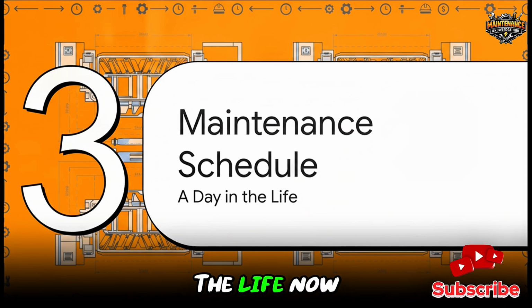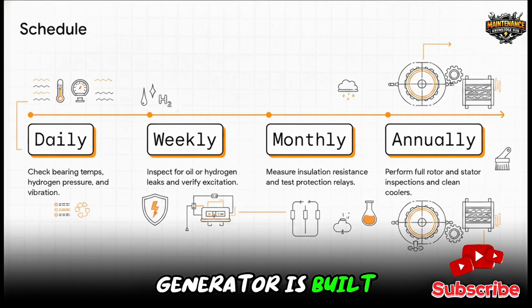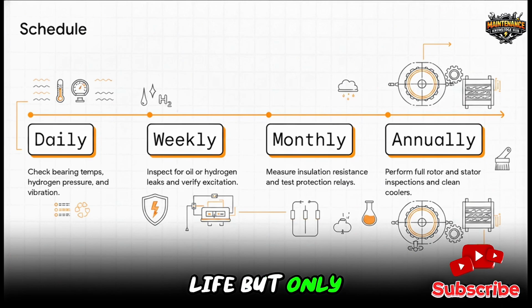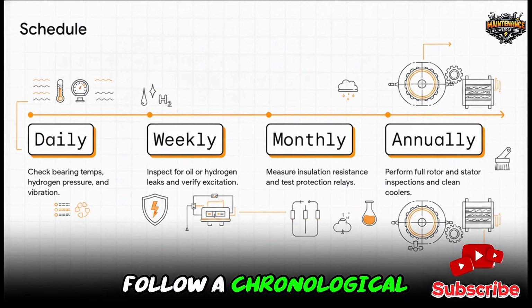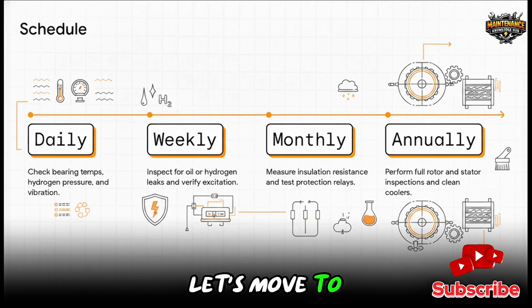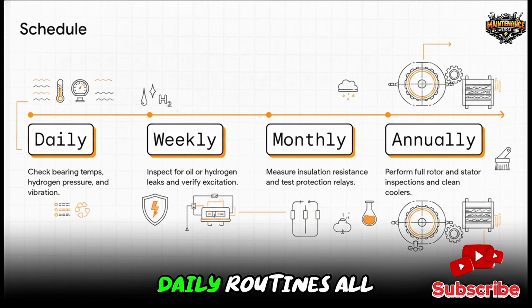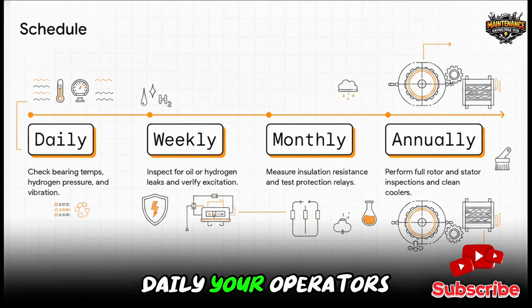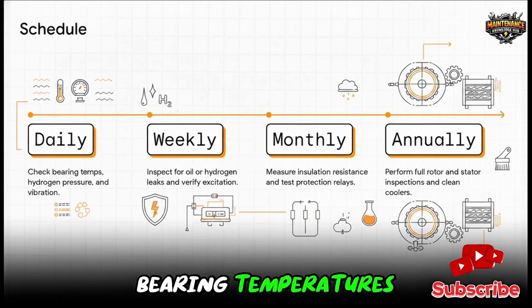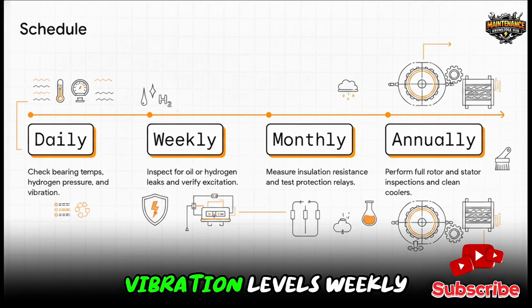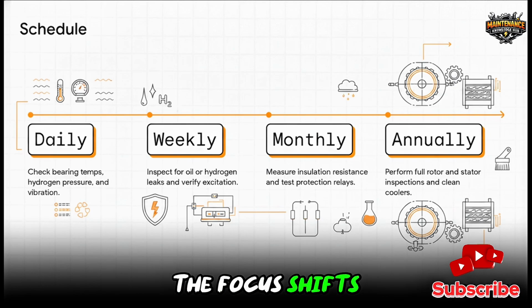A day in the life. Now, a turbogenerator is built for a long service life, but only if you meticulously follow a chronological maintenance schedule. Let's see how this builds from simple daily routines all the way up to massive annual outages. Daily, your operators are hawkishly checking bearing temperatures, stator temperatures, and vibration levels. Weekly, the focus shifts to physical, hands-on inspections. You're checking for oil or hydrogen leaks, cleaning the generator area, and inspecting cooling fans.